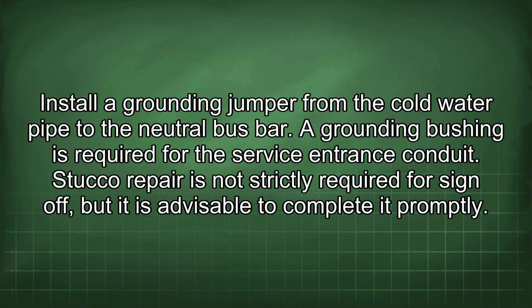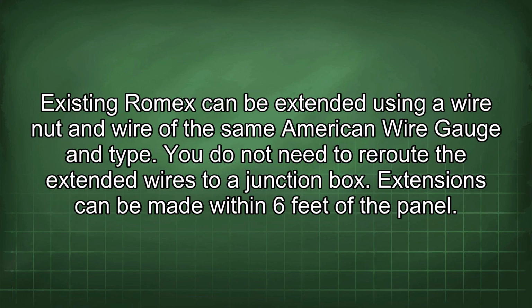Stucco repair is not strictly required for sign-off, but it is advisable to complete it promptly. Existing Romex can be extended using a wire nut and wire of the same American wire gauge and type. You do not need to reroute the extended wires to a junction box. Extensions can be made within 6 feet of the panel.